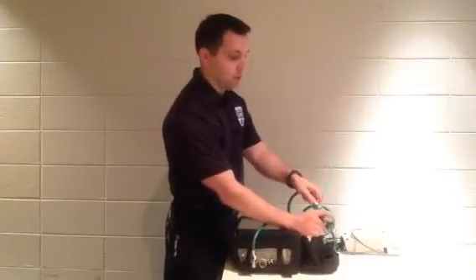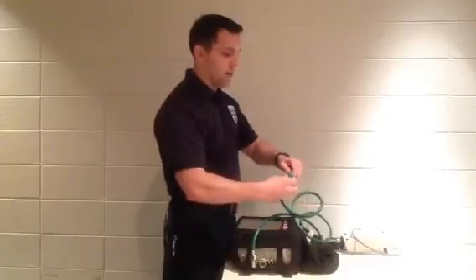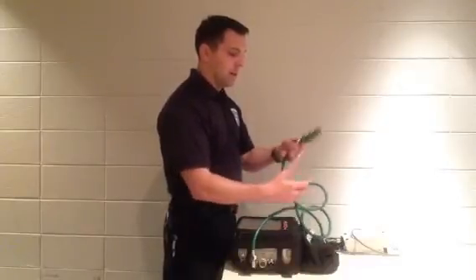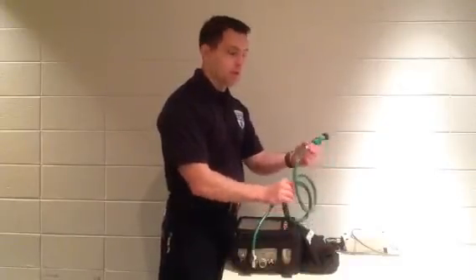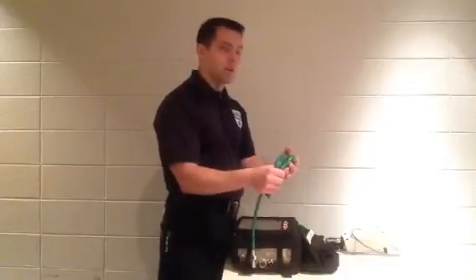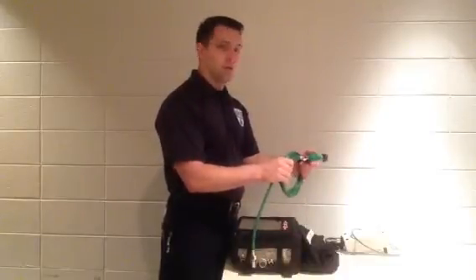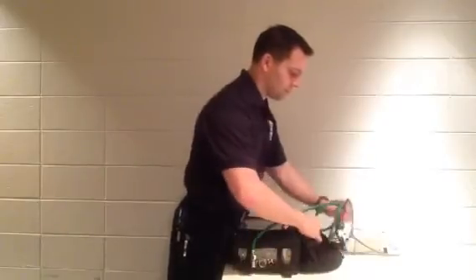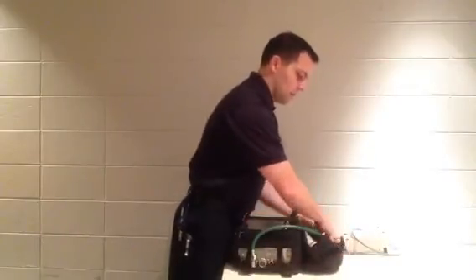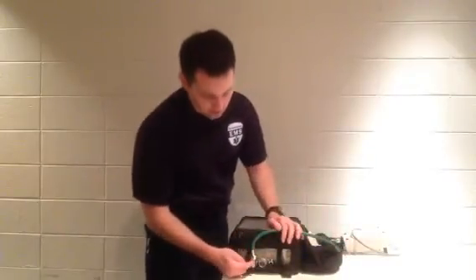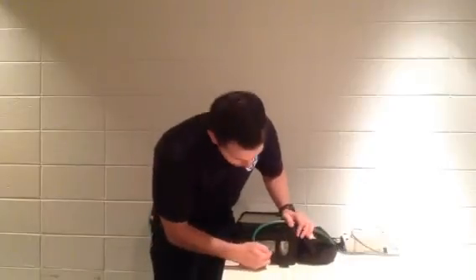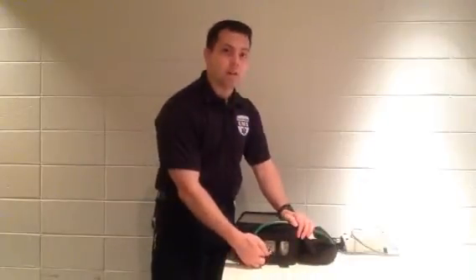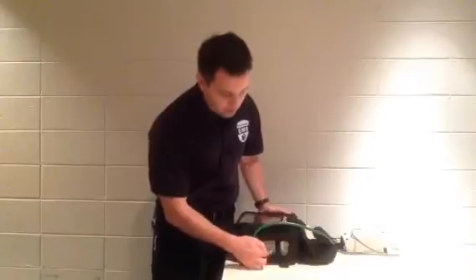So you're going to run off of portable oxygen while you're moving the patient to and from the ambulance, and then you're going to be running off of the main oxygen because these guys tend to eat down a lot of oxygen during the actual transport itself. So that's your 50 psi line connected right here. We tend to not bleed too much other gases in. It'll say air in right here.